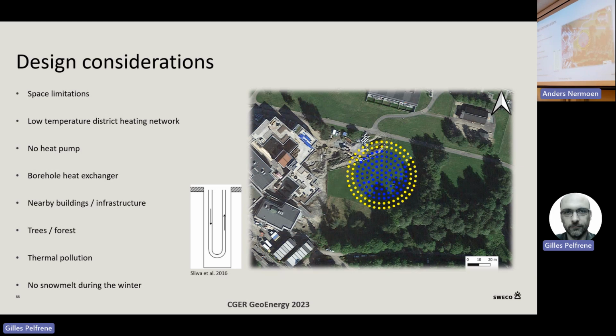One of the challenges is the borehole heat exchanger, because we are going to store up to 95 degrees Celsius, and high temperature and plastics aren't usually combined. So they're working with a Norwegian supplier, and they have a research project to find out the exact life expectancy.